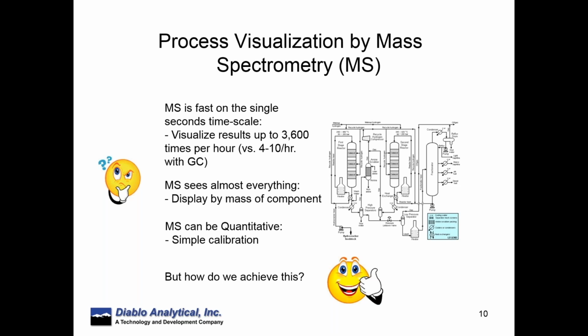And oftentimes both techniques might be complementary to looking in detail at a process. As I mentioned, the mass spectrometer can see almost everything. The exception is if you have two components that hide under the same mass, but we can see small things all the way down to hydrogen. We can see inert gases, we can see organic components, and we can certainly see up beyond the range of anything that would be considered a gas. And it can be done with this system quantitatively with a simple calibration. So now let's talk about how we achieve all of these goals with this particular device.